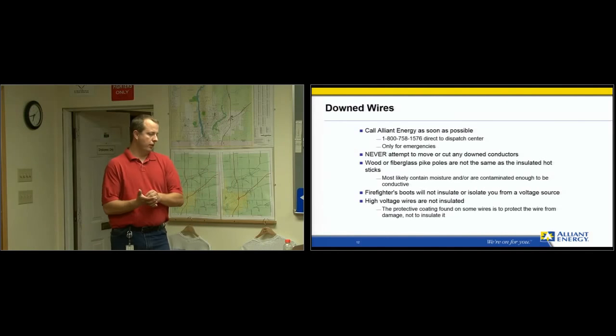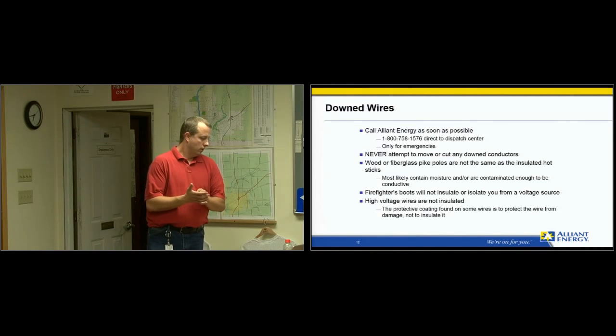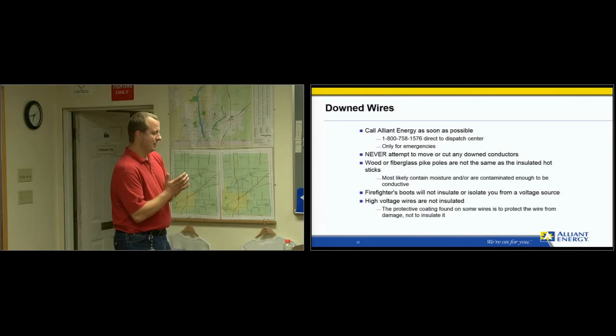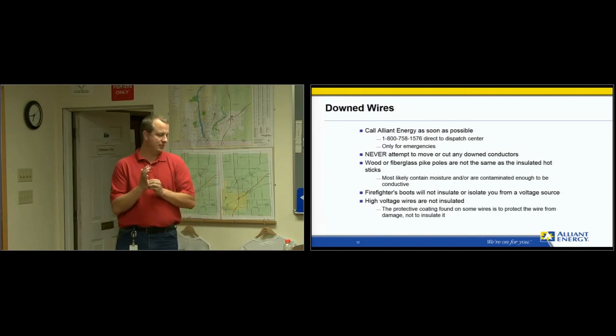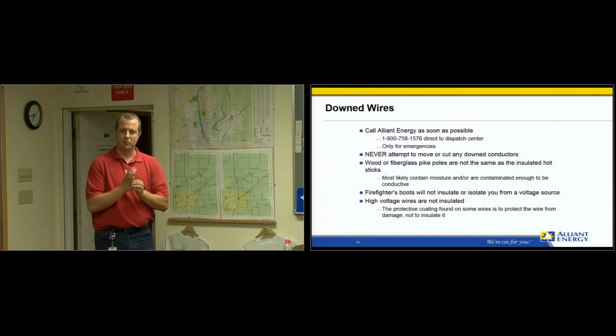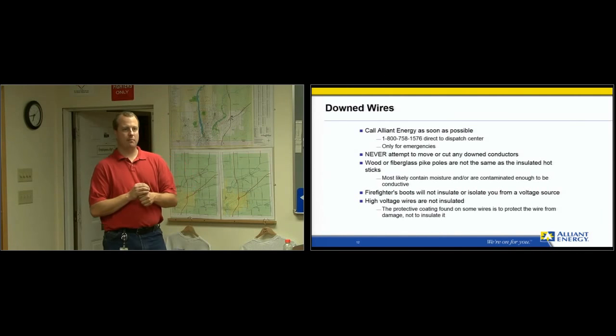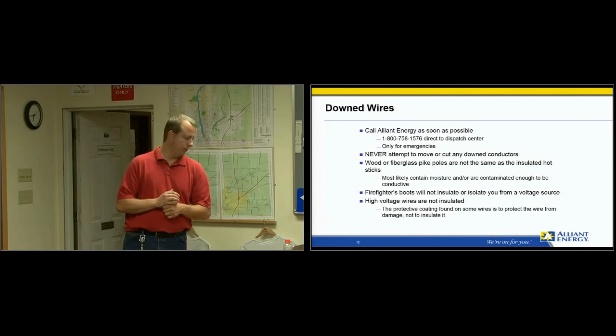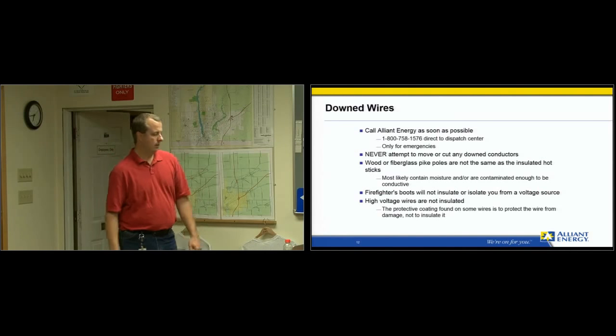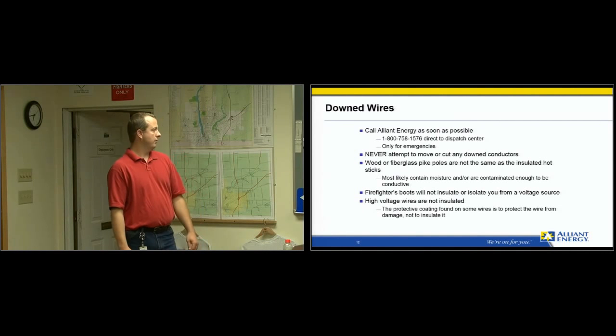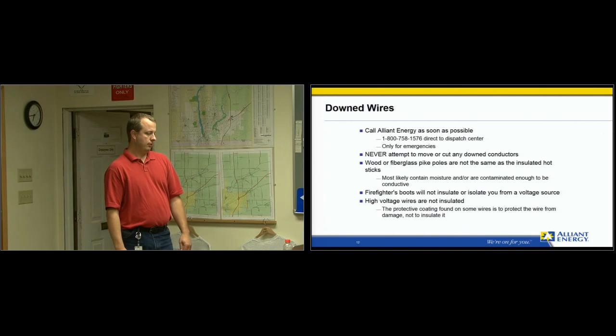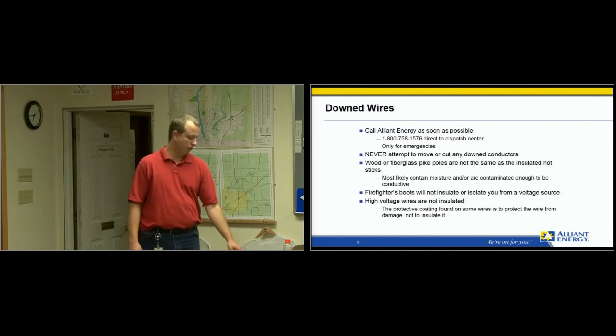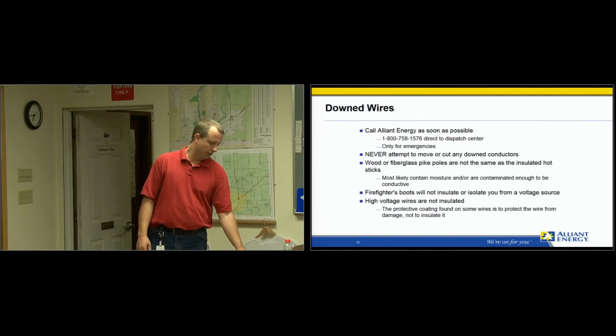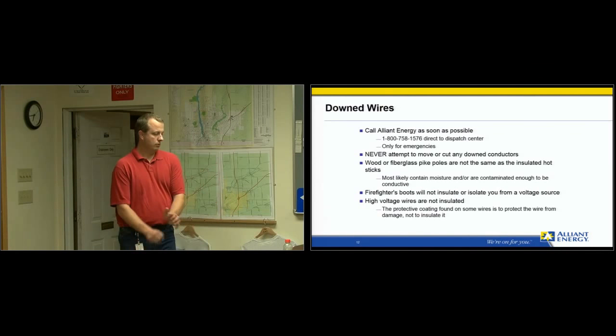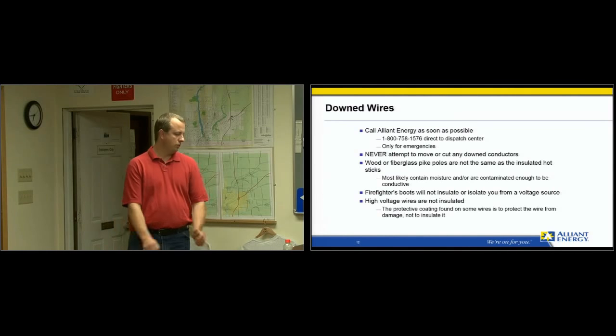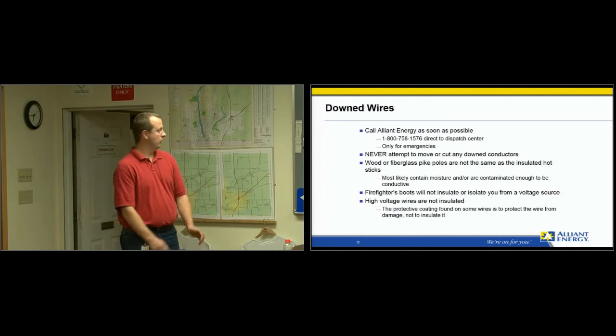Again, never attempt to move or cut any down conductors. Wood and fiberglass pike poles are not the same as insulated hot sticks—I don't know if you guys still have pike poles, but we test our sticks all the time for 20,000 volts to make sure we're keeping our guys safe. They're waxed and clean especially for that, so yours may not be as clean. Wood is an insulator, but if it's wet or dirty, it won't insulate. Firefighter boots will not insulate or isolate you from a voltage source.